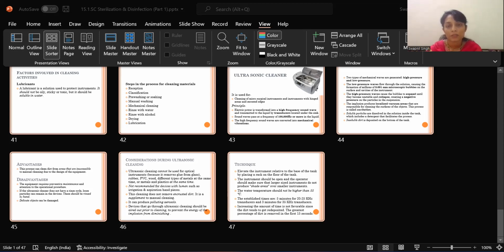Now, two types of mechanical waves are generated: high pressure and low pressure. The low pressure ones flow through the solution, causing formation of millions of 0.001 millimeter microscopic bubbles on the surface and cavities on the instrument. Then the high pressure wave cause the bubbles to expand until they become unstable and collapse and creating a negative pressure on the particles in the suspension. This implosion produces localized vacuum areas that are responsible for cleaning the surfaces of the object by a process called cavitation. Soluble particles are dissolved in the solution inside the tank, which includes a detergent that facilitates the whole process, and insoluble dirt is deposited on the bottom of the tank.